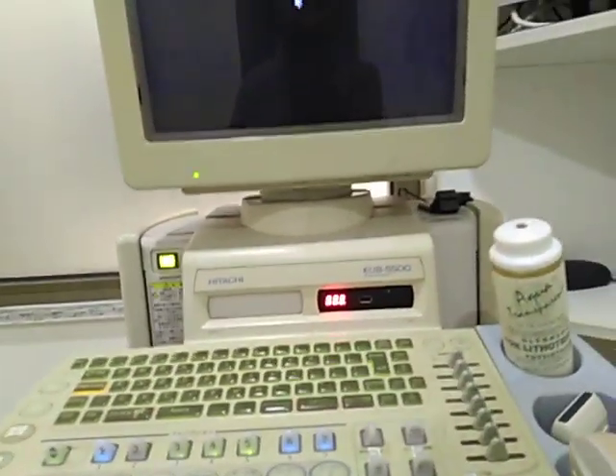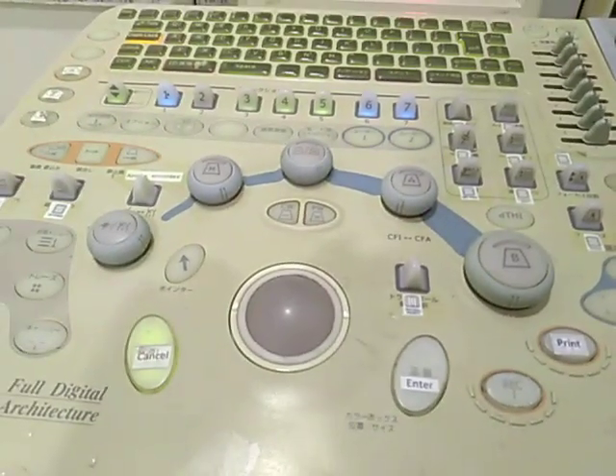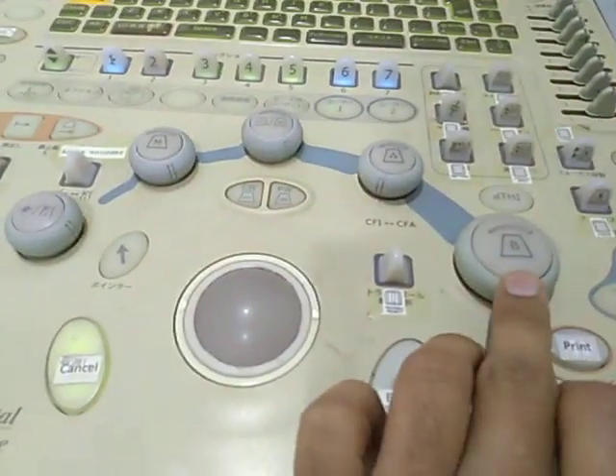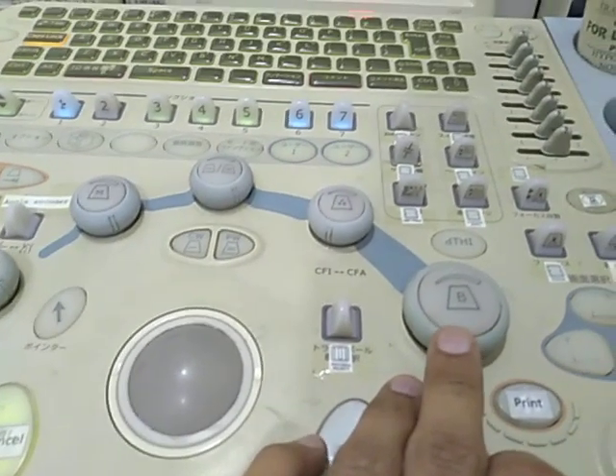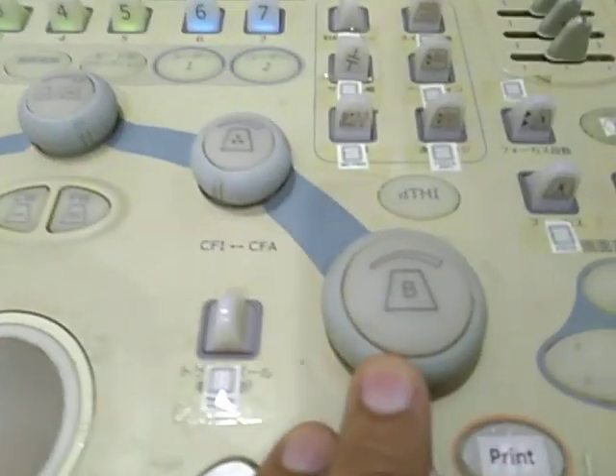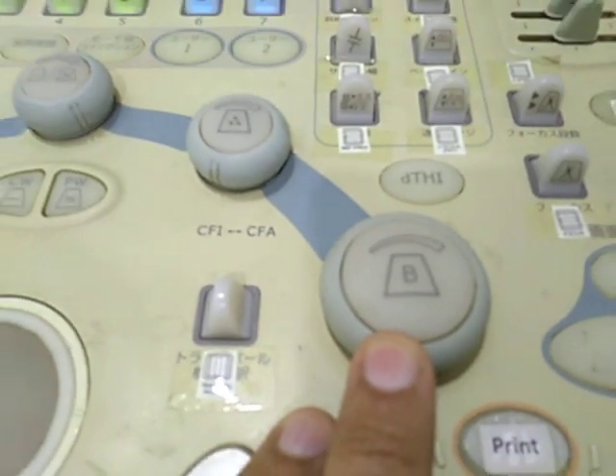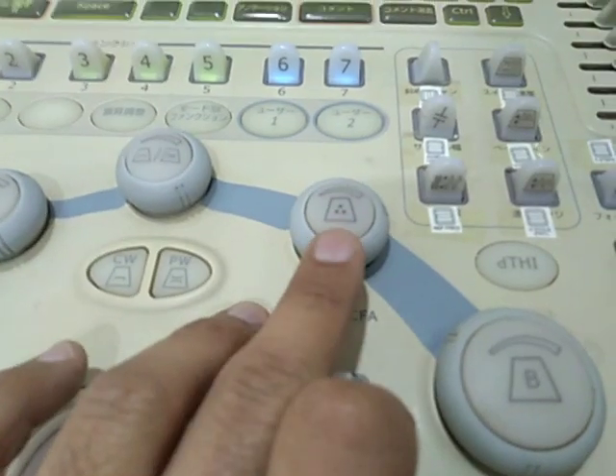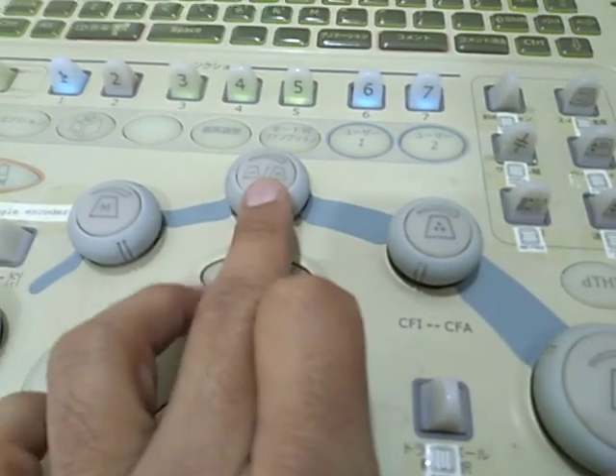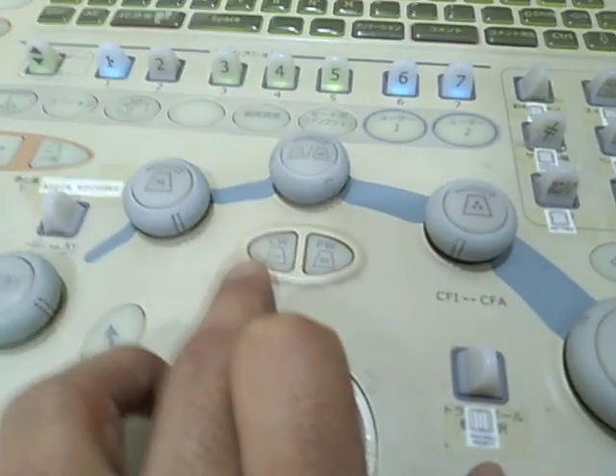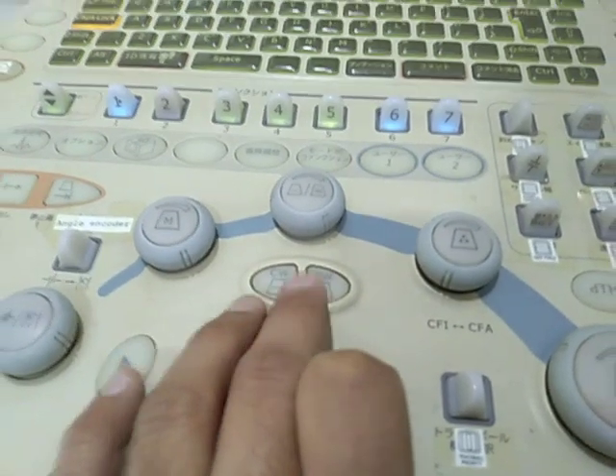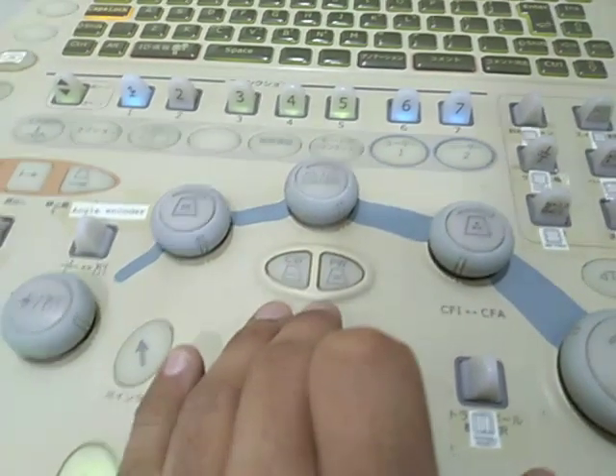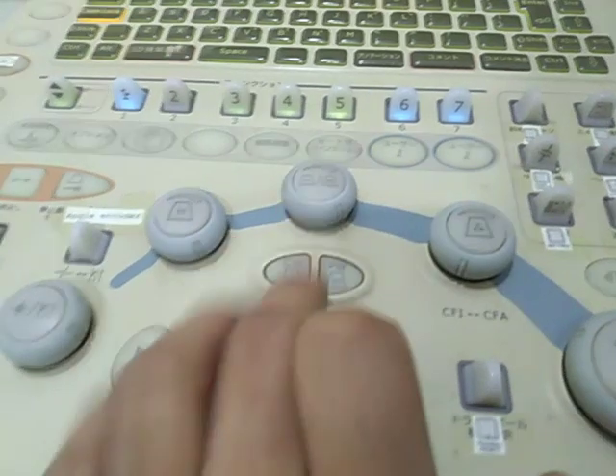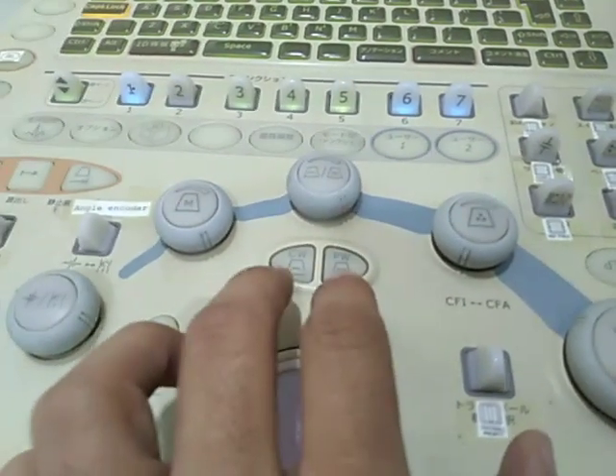Okay, so you need to turn on the unit, and let's discuss the basic modes. On the ultrasound machine, there are a lot of modes available. For example, this is called the B or brightness mode, or sometimes people call it 2D mode because it's a two-dimensional mode. This turns on the color mode. This is for Doppler mode, and in the Doppler we have continuous wave and the pulse wave. And you might have heard about the color Doppler and power Doppler and things like that. So this is all associated with the blood flow in the blood vessels.